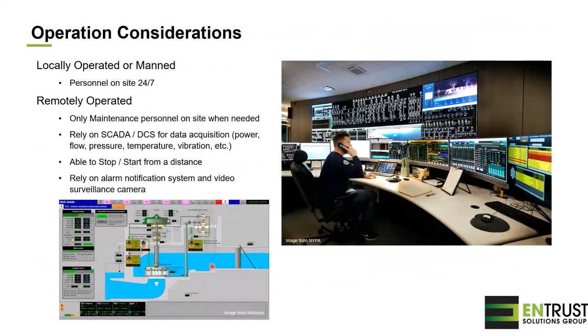Now we'll jump into the operation. Most of the operation these days is done remotely. In the past, there was always personnel on site in the old power plants because there was not enough instrumentation, but nowadays we try to operate remotely, and we'll keep the maintenance personnel on site only when needed. We will rely on the SCADA or DCS system for the acquisition of the power, the flow, the pressure, the temperature, and the vibrations. We'll be able to stop and start every unit from a distance, and we will rely on an alarm notification system and video surveillance cameras. And when something happens, we'll send the maintenance crew on site.